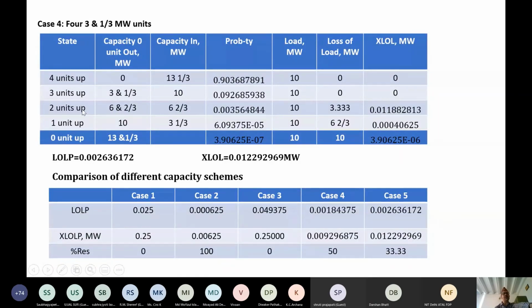When 2 units available, we have 6 and 2/3 megawatt, that is 6.67 megawatt. Capacity unavailable is also the same, 6 2/3 or 6.67 megawatt. And this particular condition occurring has a probability of this much. We have to find out according to the binomial expression. So this should be, I think, 4 p q to the power 3. Yeah, this is the third case, 6 p square q square. Yeah, and the fourth is 4 p q to the power 3, and this has this much.